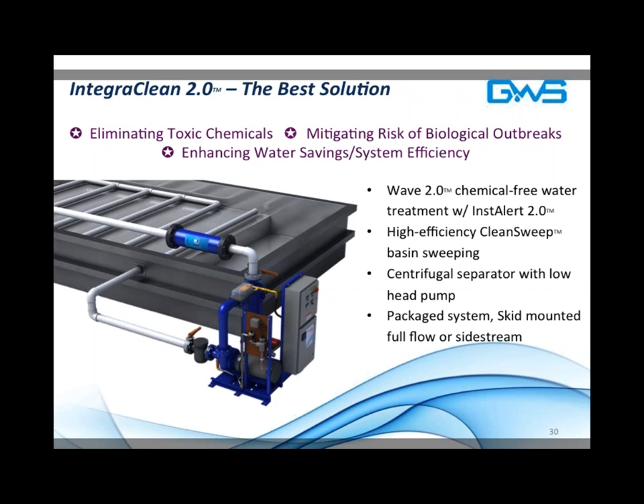That's okay. My preferred approach to our installation is literally doing a side stream application, because that allows us to essentially leave the cooling tower running for the installation process. The exception may be the installation of the sweeper system that you can see in the basin here, for example. But if you have a fairly open basin where the fill does not come down all the way to the floor, then it can be literally put in there. For existing cooling towers, you can actually go over the sidewall of the basin. We do not need to make perforations in the basin sidewall, and so installation is very quick and very straightforward.